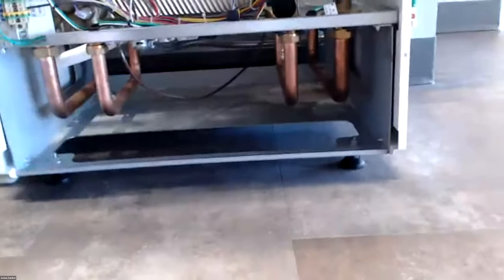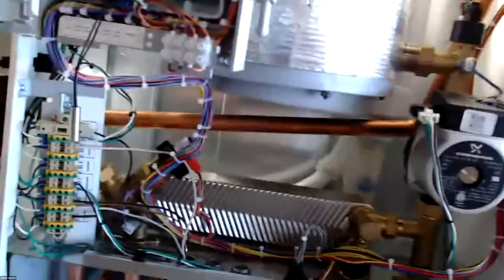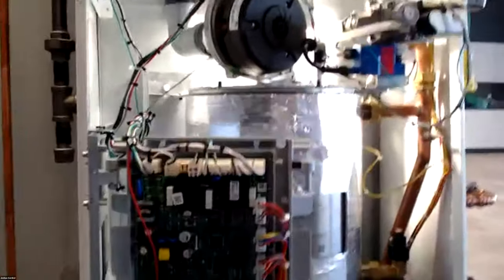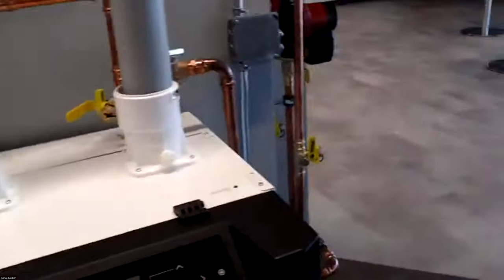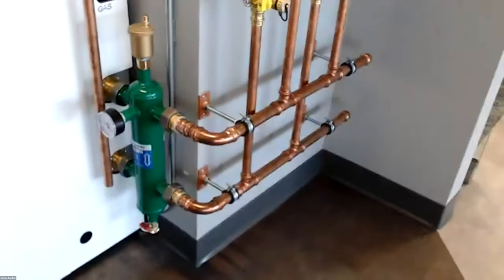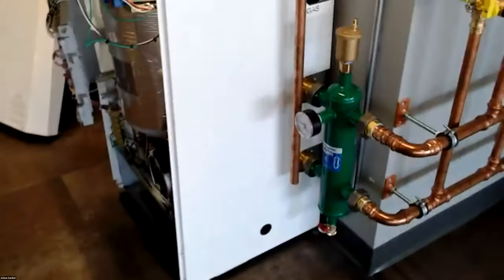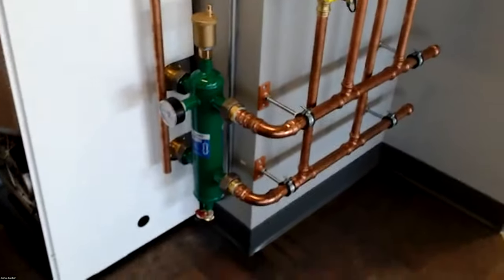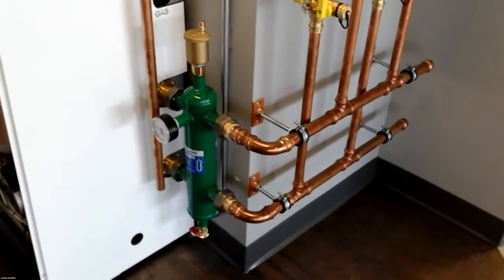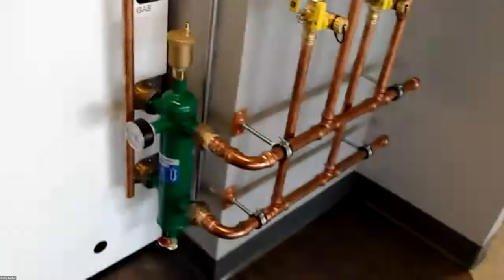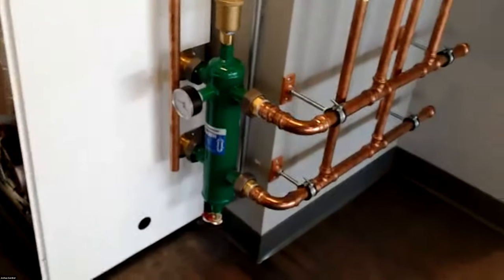Then on the bottom, like I said earlier, we have our water connections down here and there's drain points underneath there. Condensate traps located inside the unit. Other than that, it's pretty much the same thing. That's the floor boiler. Not much else is different. Same setups and everything that we do on the wall boilers. Same combustion specs, except with this one, as you can see, we're just coming off, going in our supply, coming back with a return. So all our primary piping is done. So our hydraulic separation, air separation, dirt separation is completed out of the box. So yeah, you'll pay a little bit more for this boiler up front, but you'll save a bunch of money in the labor and the piping and the materials because it's already finished.